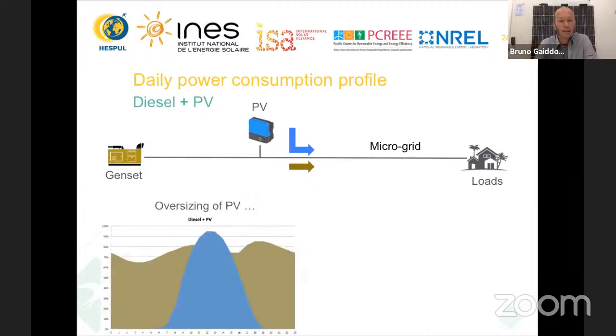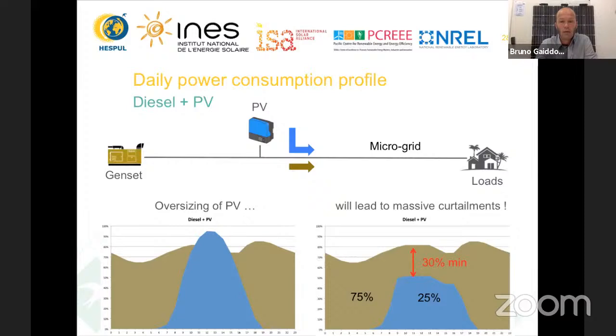If you oversize the PV system, due to the control system and regulation, you will not produce more electricity. You will curtail production and lose a lot of it just to keep the genset operating at its minimum 30% power. So that's a problem, and this is the limit of the hosting capacity of a diesel microgrid.